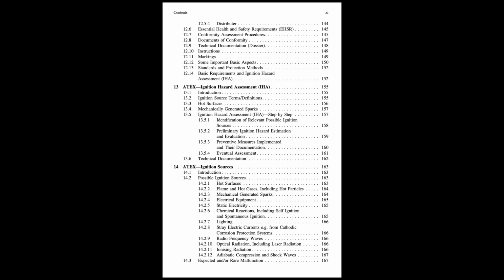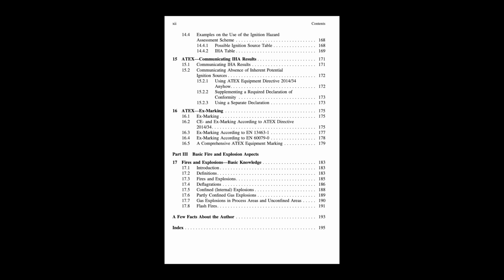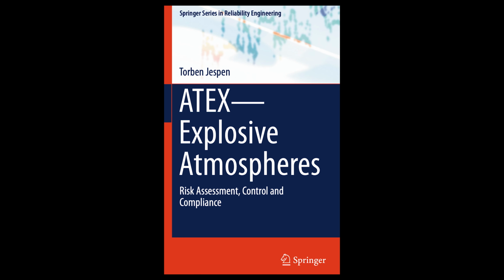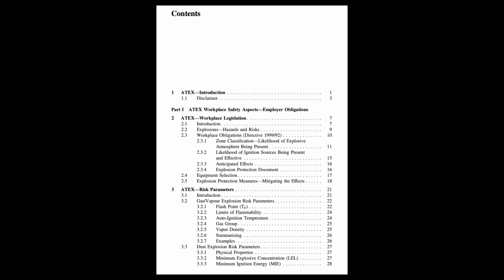Well, that was a truly comprehensive deep dive into the world of ATEX and explosive atmospheres. Just to quickly summarize the big picture, we've really explored why prevention, stopping those atmospheres forming, is always priority number one. Absolutely. We've seen how crucial those thorough risk assessments are for identifying and evaluating all the potential dangers. Foundation, yeah. We've looked at the specific, sometimes sneaky hazards from dusts, and especially static electricity. Often underestimated. And the whole logic behind classifying areas into zones, and then the absolutely essential principles for selecting the right equipment with the right protection and the correct marking for use in those zones. Connecting the risk to the solution.